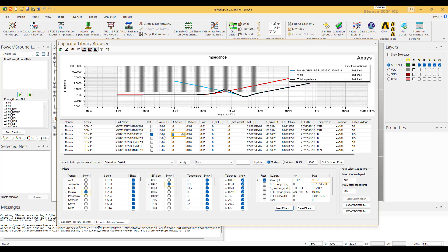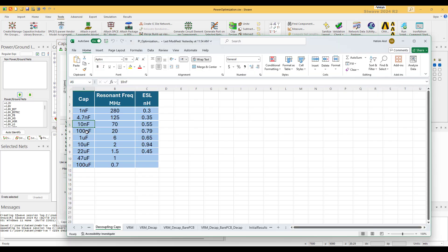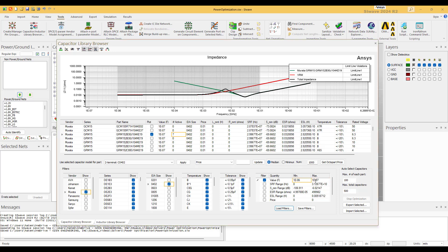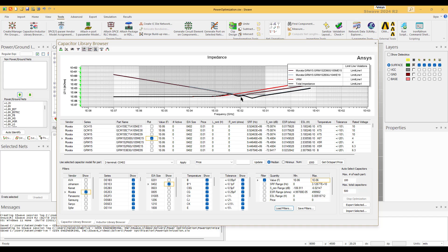Remember, we don't want to optimize the VRM. All what we want is to lower this curve to a reasonable level. So we added this. Now we have a hump here, so we go to the next one in the list and we go with one microfarad.